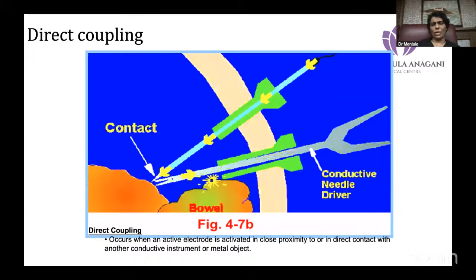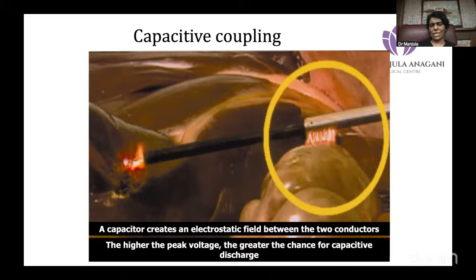So direct coupling is one: inadvertently you're touching one instrument to the other, and that instrument is touching something else. The capacitive coupling is the most important thing because we start using a lot of steel cannulas. That is the most dangerous thing. Wherever you want to use an energy source, please use plastic cannulas. Why is it so? The capacitor which is created there will cause a capacitance, because two conductors, when separated by a non-conductor, also become like a conductor. The higher the peak voltage, the greater the chance for the capacitor to discharge.